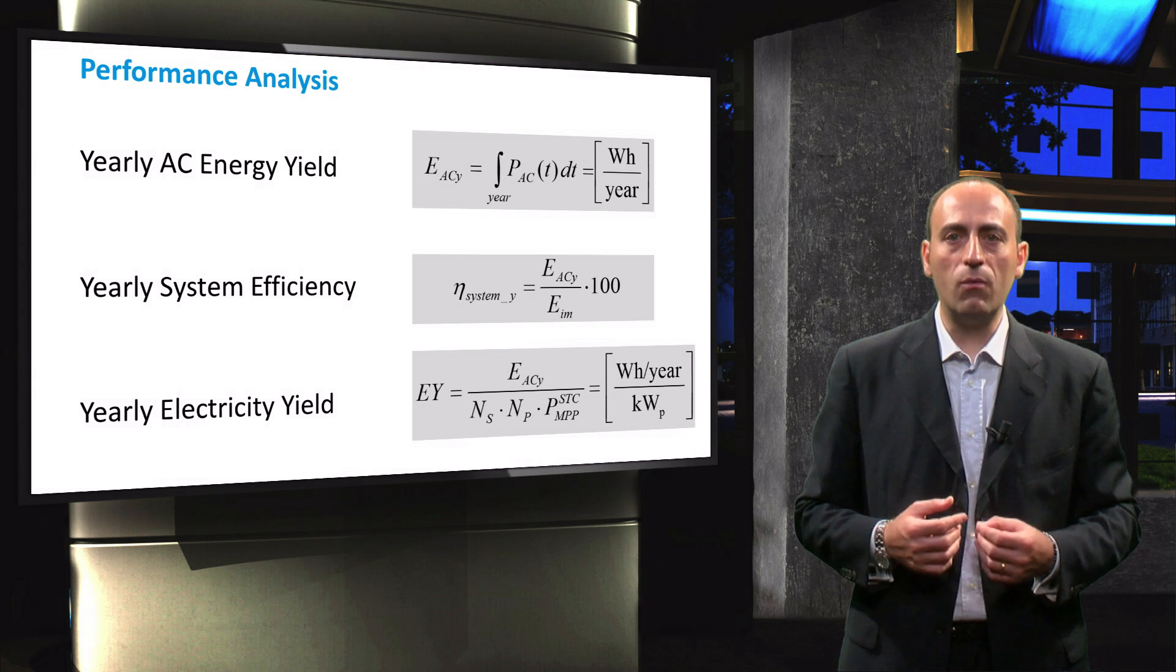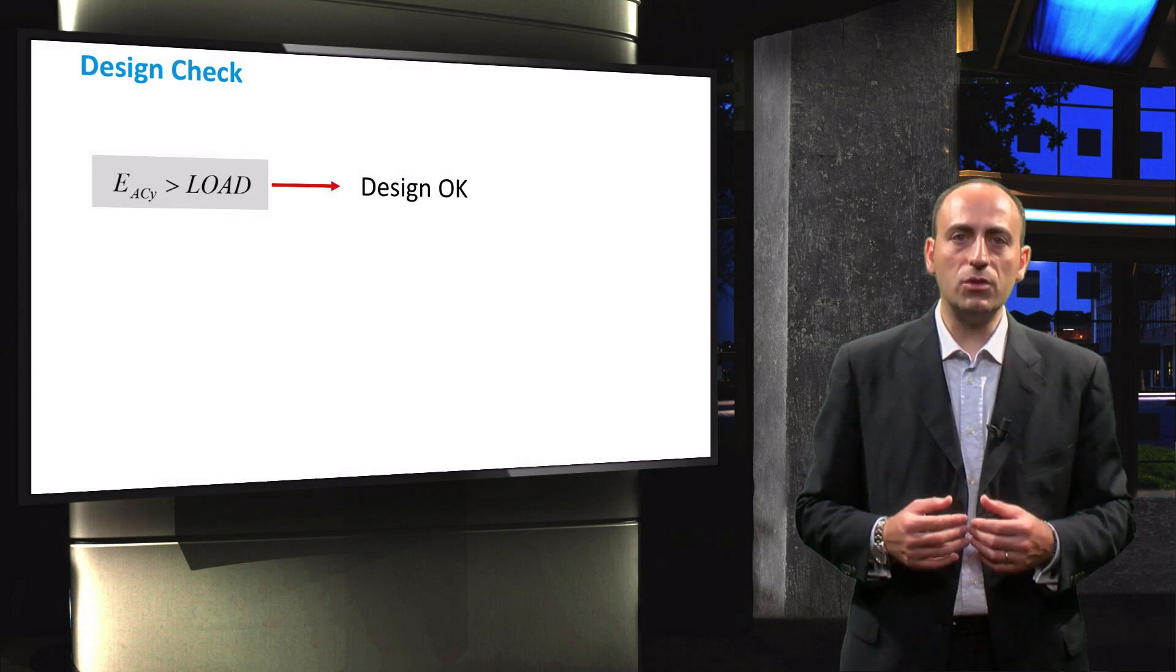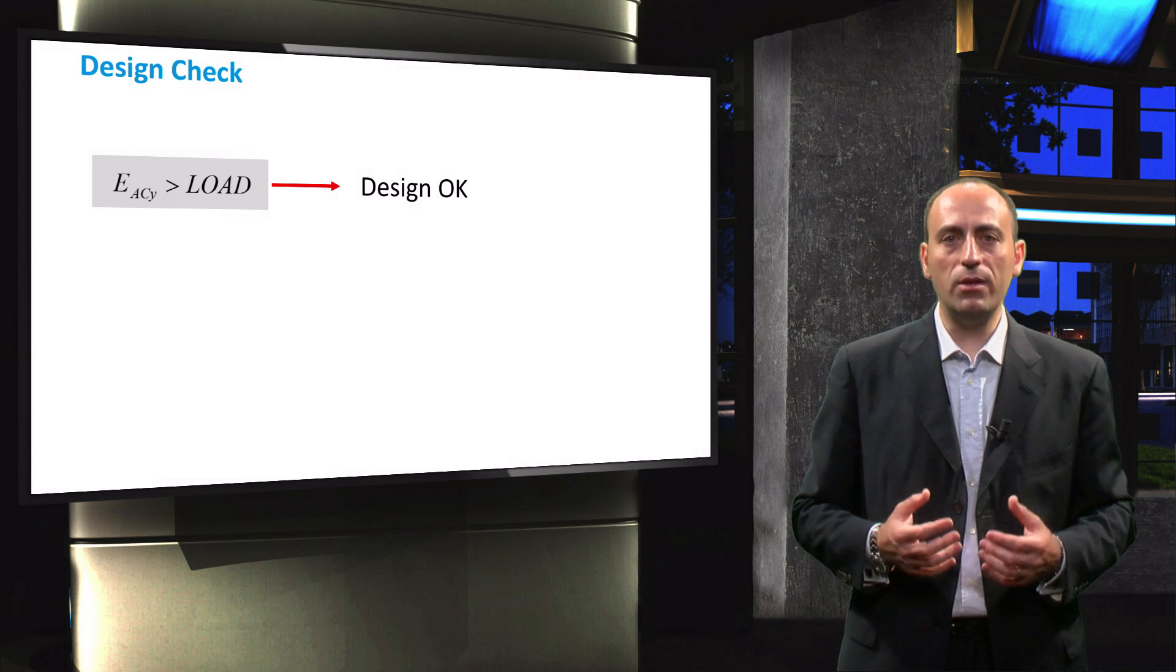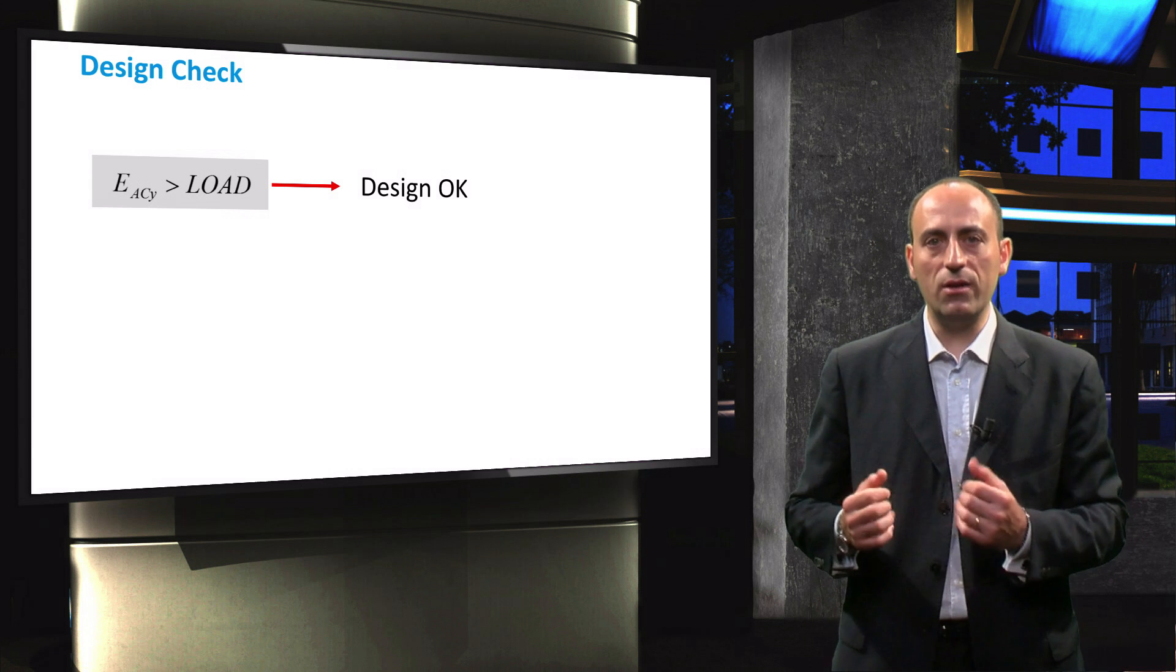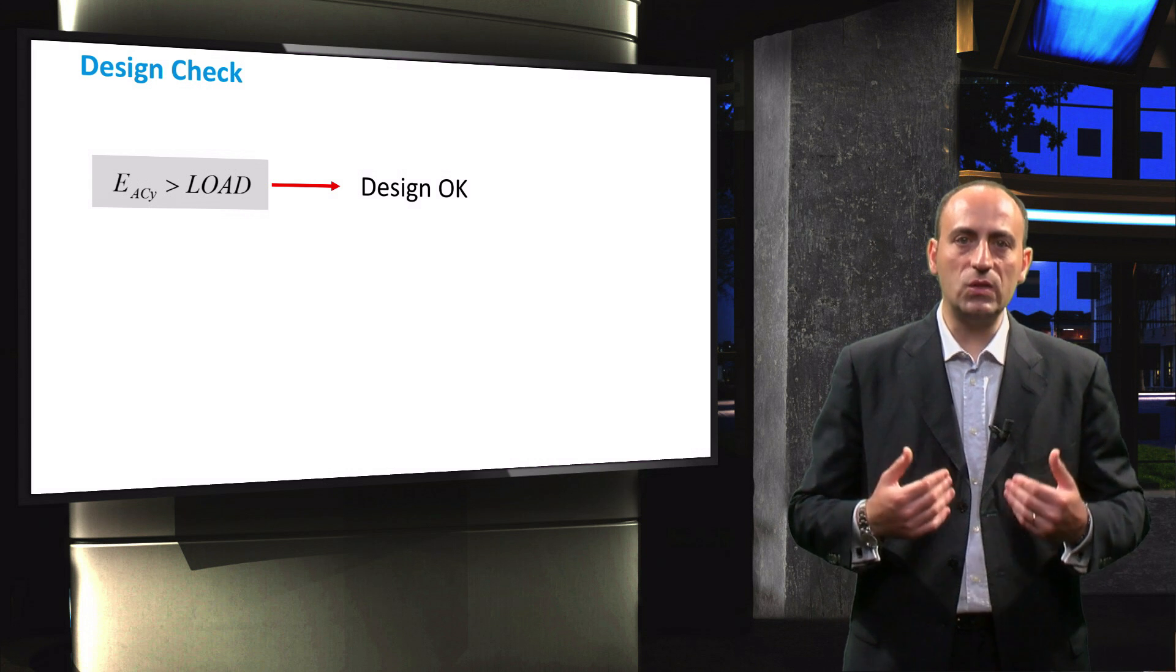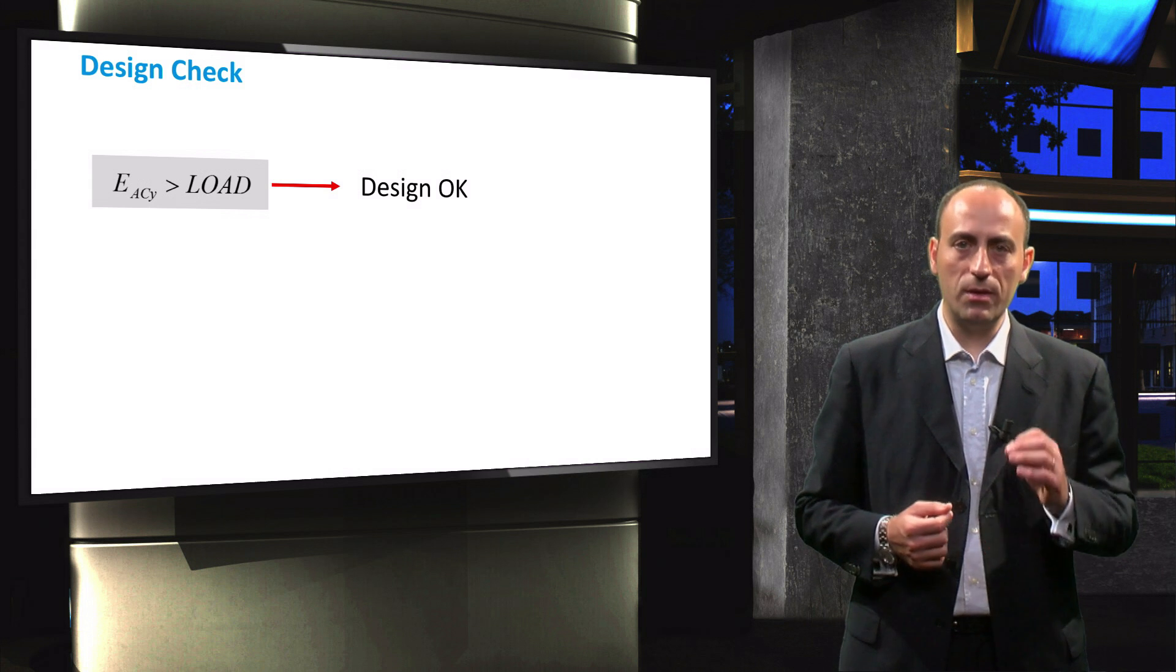The final step involves checking the design. We compare the annual energy generated by the PV system against the energy consumption of the loads. If the energy generation exceeds the load demand, the design of the grid connected PV system is approved.